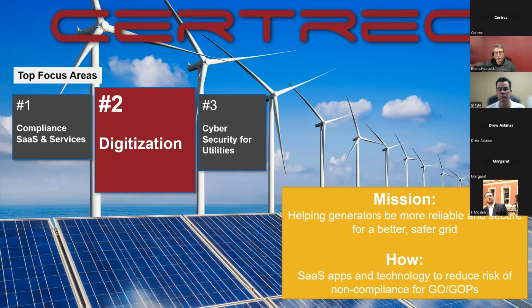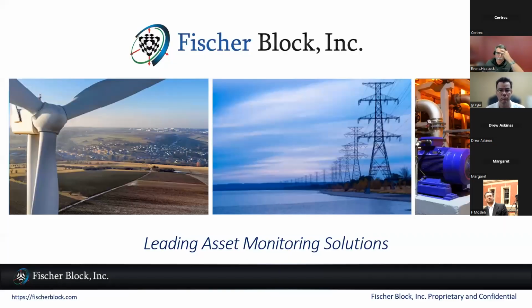But the big one today really is digitization and how we are handling that information. Again, Fischer Block is a big part of that, as it will help take information that's analog, digitize it, and then make it available to you to help you with various things, in particular predictive analytics. Again, we want to help the generators be more efficient. Like I said, Fischer Block is across the industry. It's not just power, but generation, transmission and distribution, and also industry. The nice thing about Fischer Block is that it can actually look at what's going on with the motor. It does analytics based on the signatures from the current and voltage, and it'll help you determine if you need to do preventive maintenance way before the motor or pump destroys itself, say. Worst case, going back to our initial opening of the broken blade on that wind turbine.